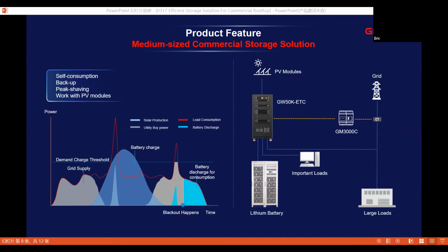Also, if this inverter is for commercial use, we have the peak shaving function. You can set the maximum power from the grid. For example, you can set 20 kilowatts from the grid. If the load consumption is more than 20 kilowatts, the battery will discharge to support the load to make sure the power from the grid is less than 20 kilowatts. So this is related to the electrical bills for the commercial rooftop.